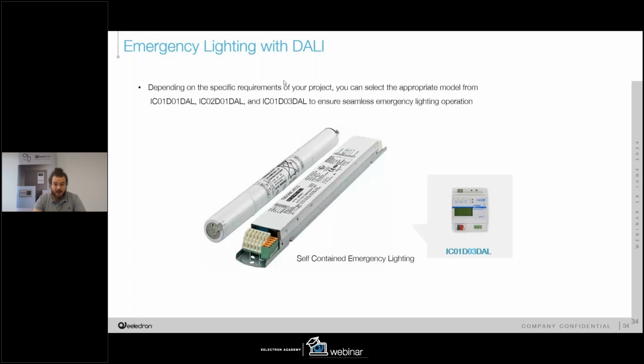Starting from the ballast with self-contained battery, in this case we have to propose mandatory our IC01, D03, DAL, because it's the only gateway that we have in our portfolio that can read the information about the battery, check the battery status, but also perform tests. So during the day, the gateway can ask the lamp to go in test mode, keep the light on for 1 hour, and give back the percentage of the battery after the test. So this can be done directly from the gateway itself.